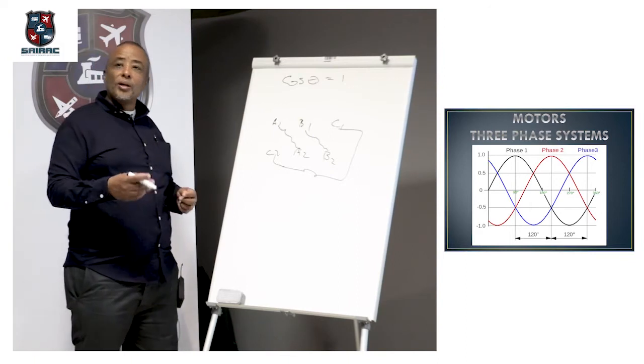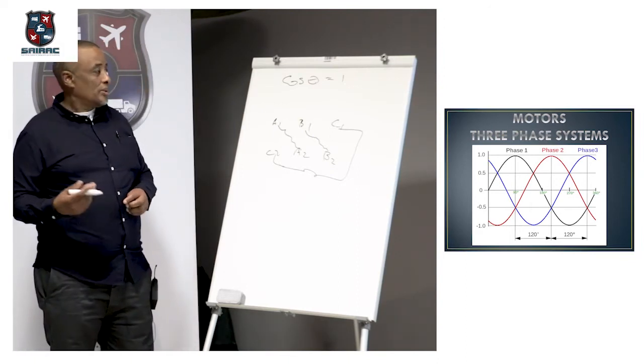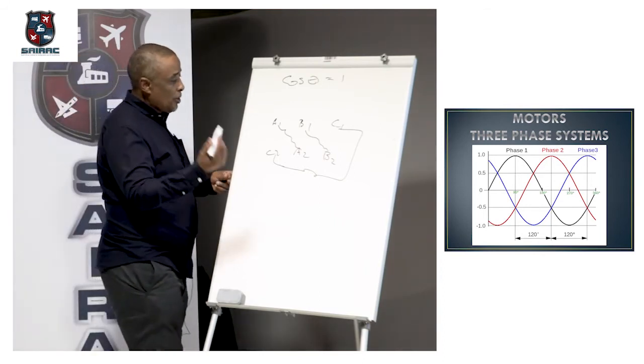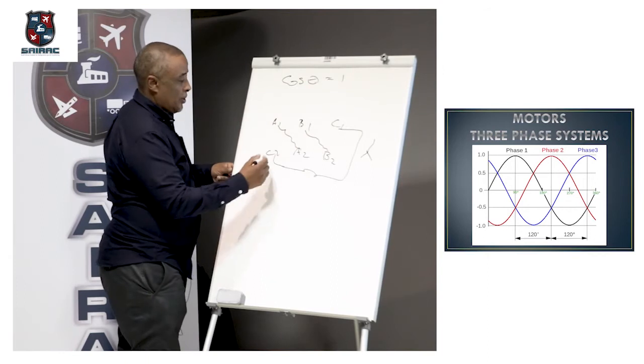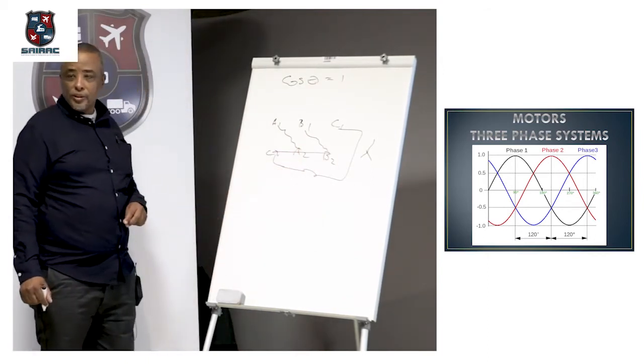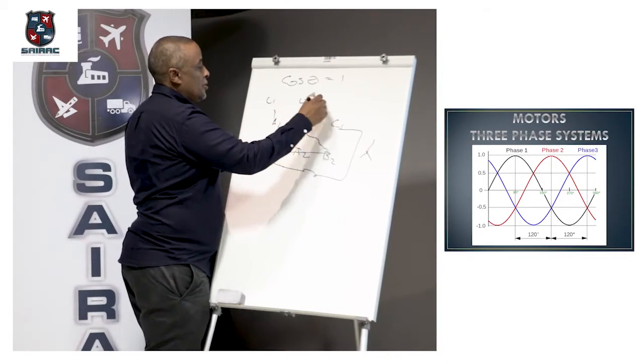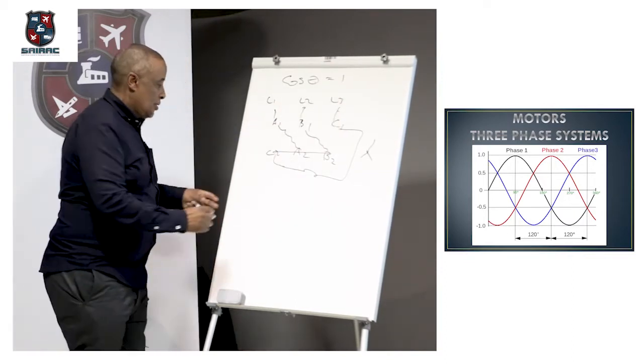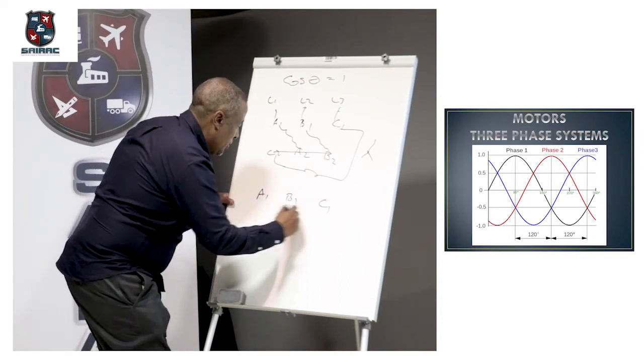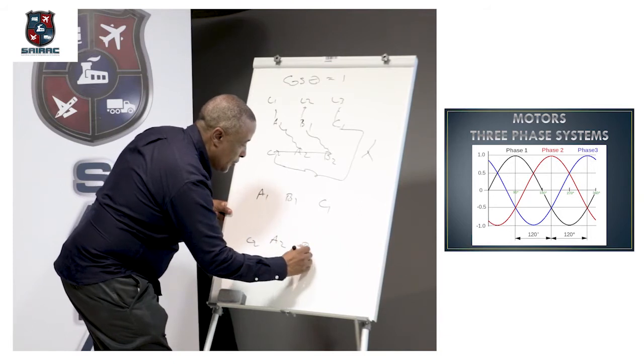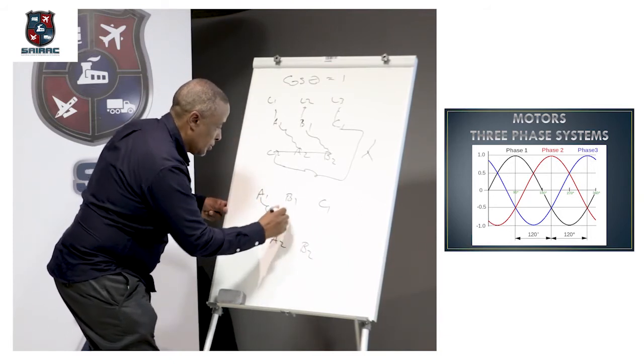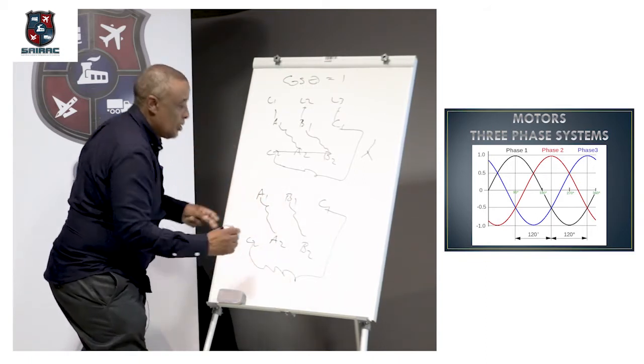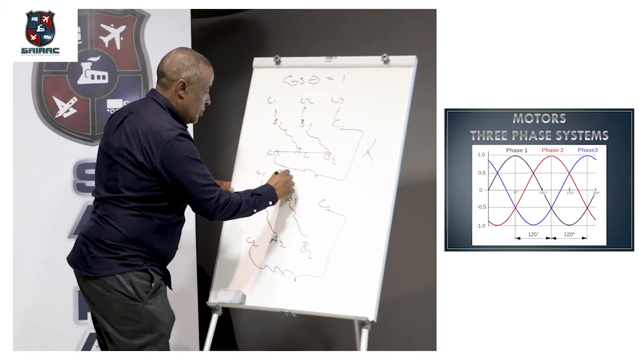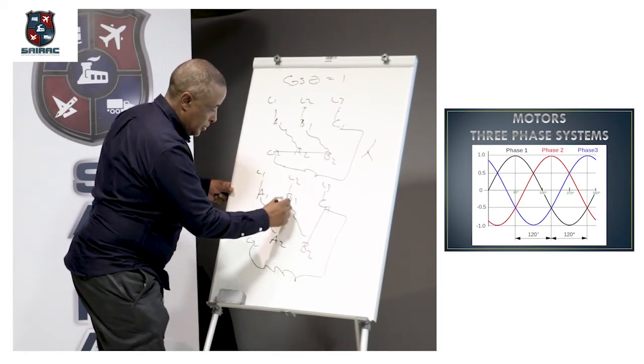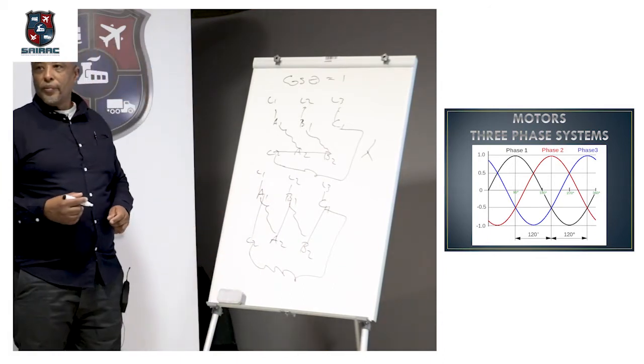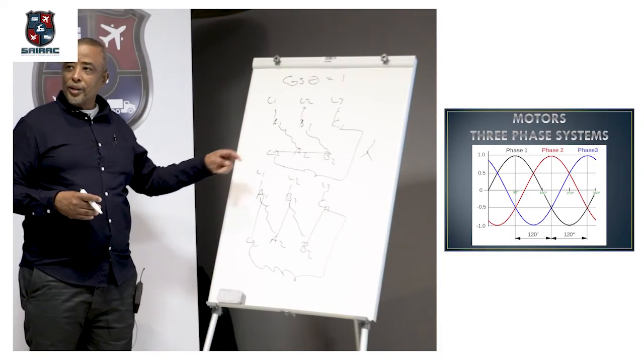Do we connect up the motor in star or do we connect it up in delta? Okay, later on we'll do the starters. Okay, if we want to connect it up in star, let's put a bridge piece across. There's your line 1, line 2, and line 3. On the other hand, if you've got A1, B1, C1, C2, A2, B2, okay, in delta, okay, that's the motor by itself, connected up either in star or delta.